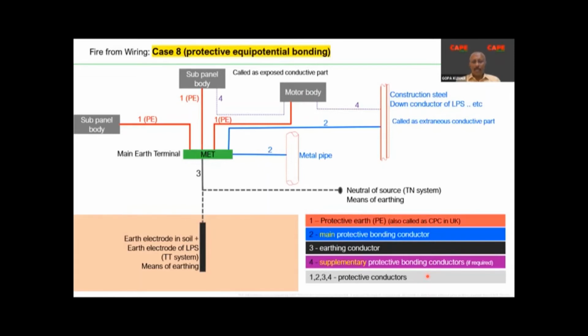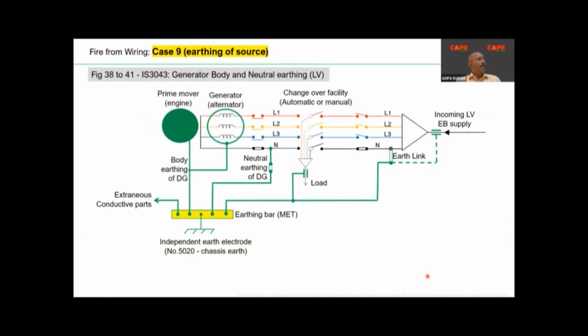To avoid such hazards, protective equipotential bonding is mandatory in every electrical installation, and in the hospital, it's very critical. Number 9, earthing of the source. During this COVID time, I have visited, not for an audit, but just to guide some of the hospitals. I visited a few hospitals, and we were going through this particular subject, earthing of the source.